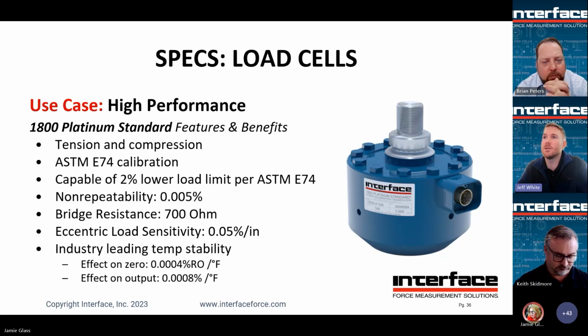You'll notice the bridge resistance. Normally 350 ohms is standard. This is 700 ohms. This is because we use 16 strain gauges, twice as much as a normal load cell, and that gives us the enhanced moment sensitivity. And it is as good as it gets regarding temperature deviation during testing.